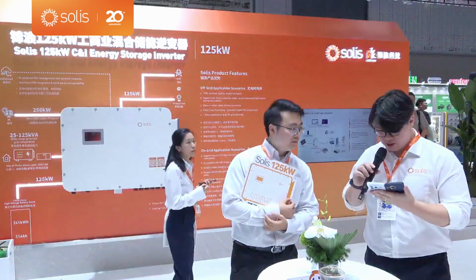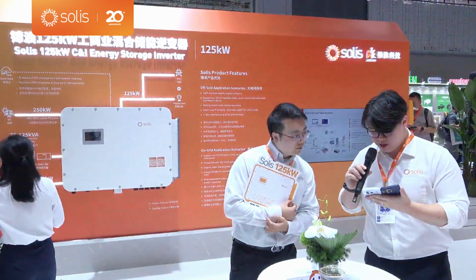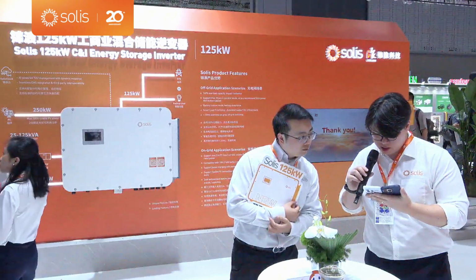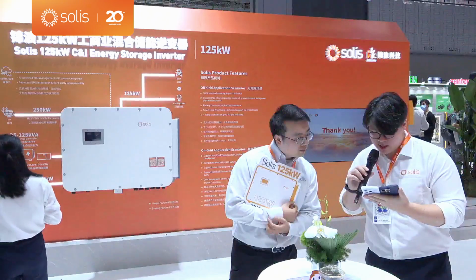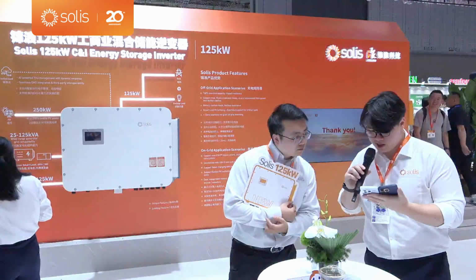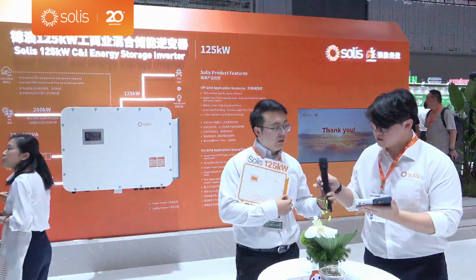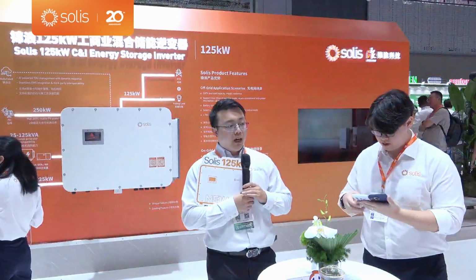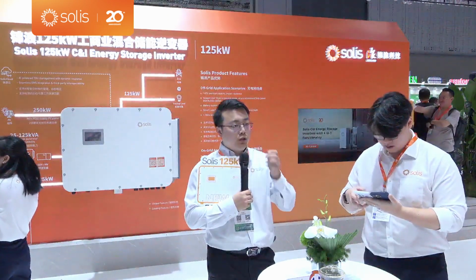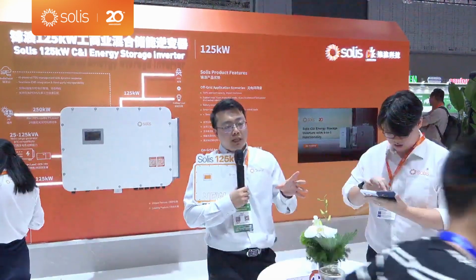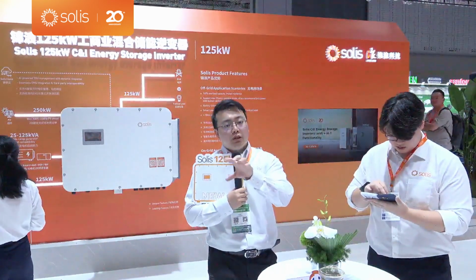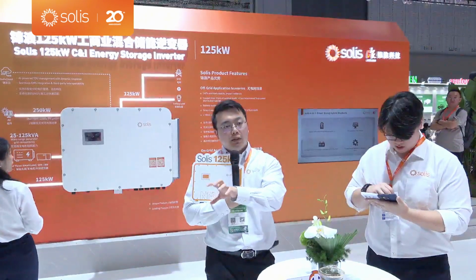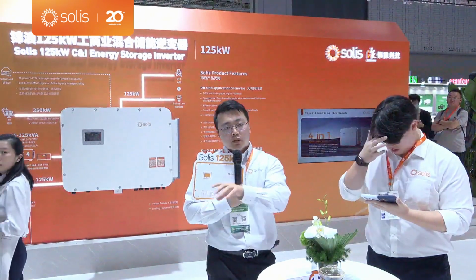We have a few more questions left from the audience. We are still in the 50 kilowatt inverter question. Another question is, is there a recommended battery capacity range for pairing with the 50 kilowatt? Okay. For 50K hybrid systems, typically in a CNI scenario, customers will use a 2-hour battery or a 4-hour battery. That means if you have a 50K hybrid, normally you can pair with 100 kilowatt hours of battery or 200 kilowatt hours of battery.